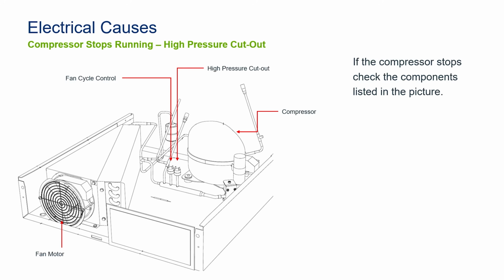You turn the machine on, contactor snaps in, compressor's running, keeps running, stops. Fan never kicked on. Well, we have one of two problems. Either we have a fan switch that's not calling for the fan, or we have a fan motor that cannot run. The way that I typically will troubleshoot that is I will pull the wires off of the fan cycle switch, assuming that I have verified the high pressure switch right next to the fan cycle switch is not open and causing our problems. You could be seeing something with a contactor that's having a problem, but you'd have to take voltage. Again, I do it without the bin, just so that way I had room to do my work.